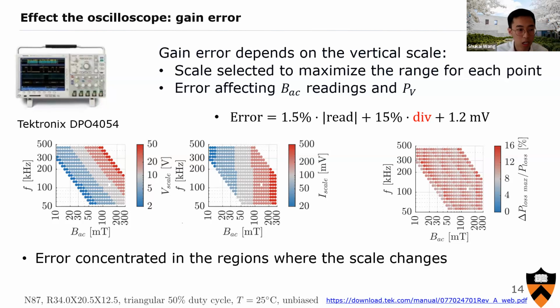But if you calculate the loss, which uses both the voltage and the current measurements, then your loss error will be contributed from both. If you check how smooth the data is on the right side here, you can see that the most abrupt changes usually happen near where the scale of the scope changes, which is when that division error plays a bigger role. So to wrap up, we really should pay attention to this type of error when it comes to scope selection, as this 15% is quite significant.